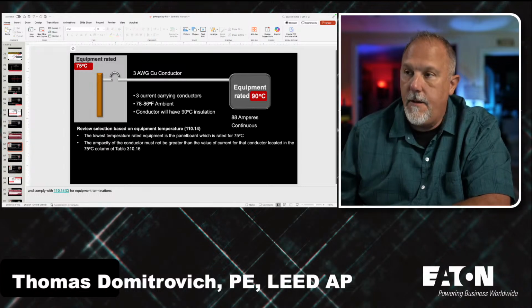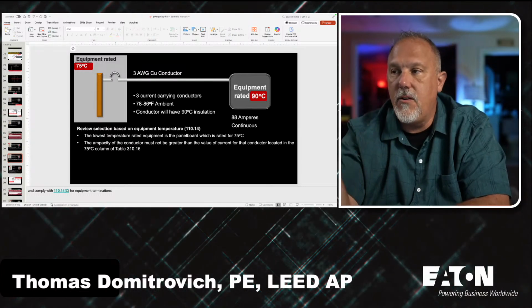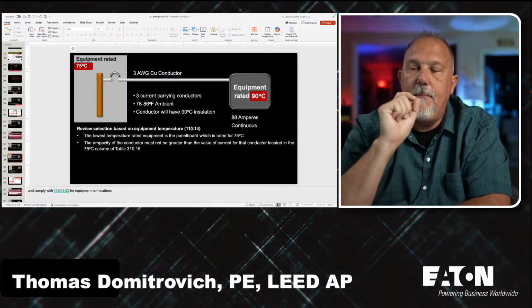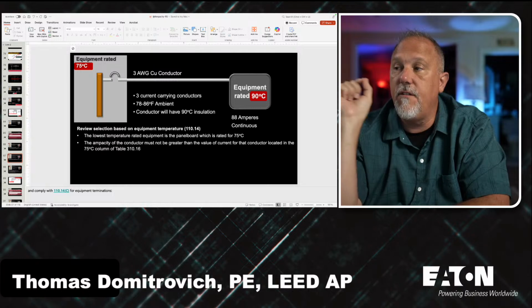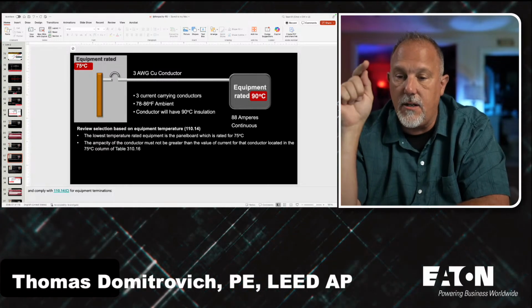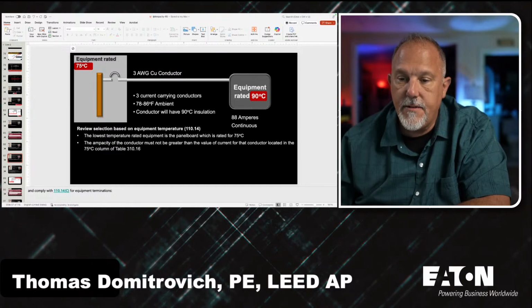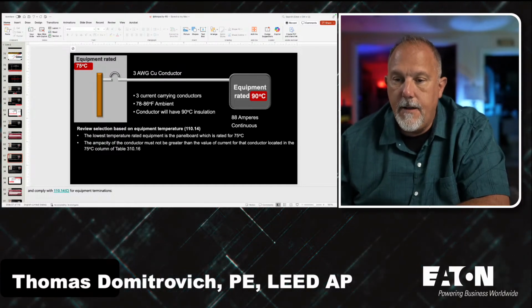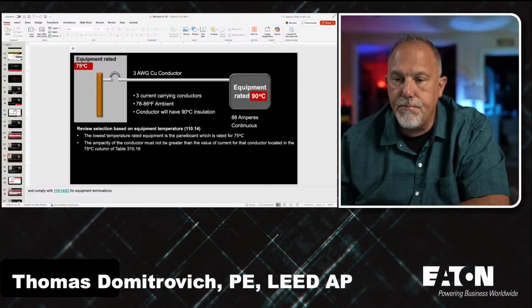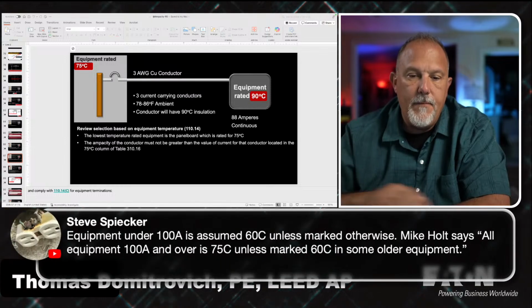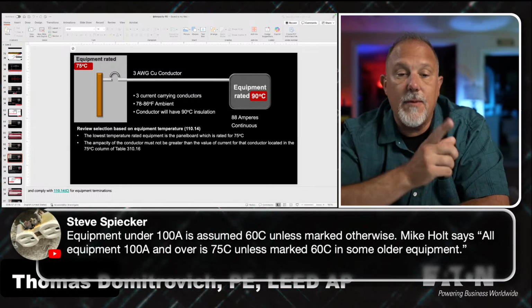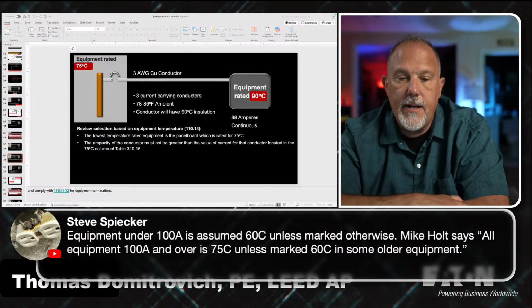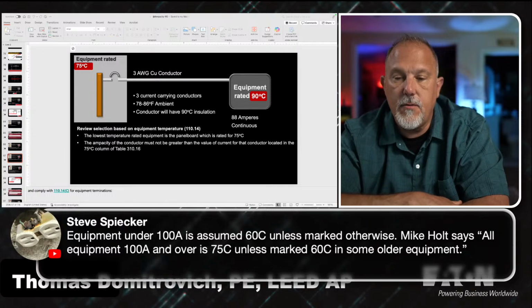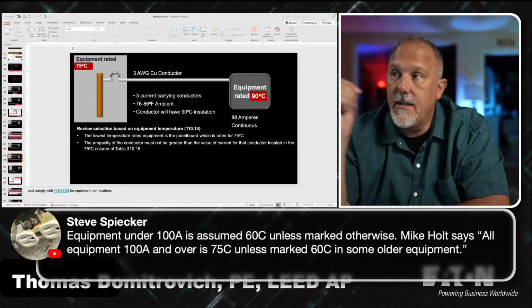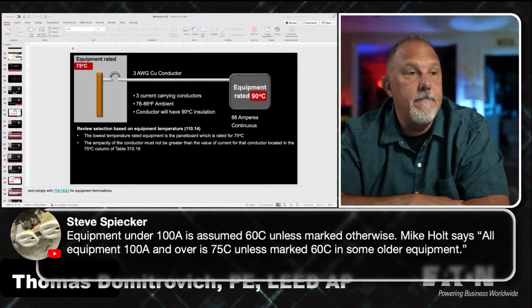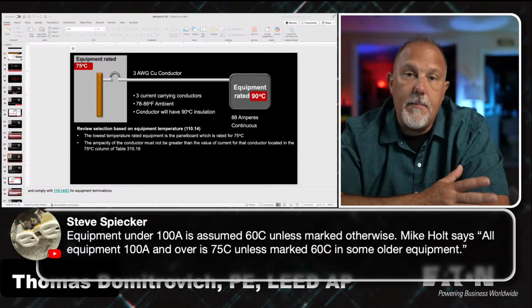Okay, so the lowest temperature rated equipment is the panel board, which is 75 degrees C. The ampacity of the conductor cannot be greater than the value of current for that conductor located in the 75 degrees C column. Equipment under 100 amps is assumed 60 degrees C unless marked otherwise. That's what I would say, Steve. All equipment 100 amps and over is 75 unless marked 60 degrees, in some older equipment. Yeah. But in this case, my equipment is marked 90 degrees C, and that would be per its listing.